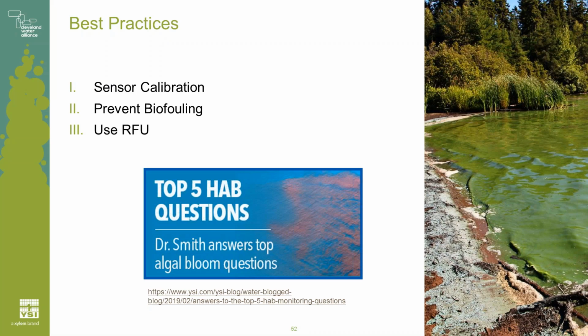But the funny thing is that in practice, a lot of these really detailed questions are rarely the types of things that trip users up. The most fundamental things like calibration, fouling, and really understanding what the units of measurement are telling you are what prevent people from getting the most out of their algae monitoring. So in this last section, we're going to touch on these 3 things.